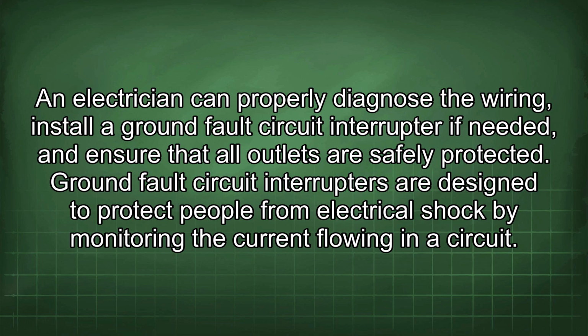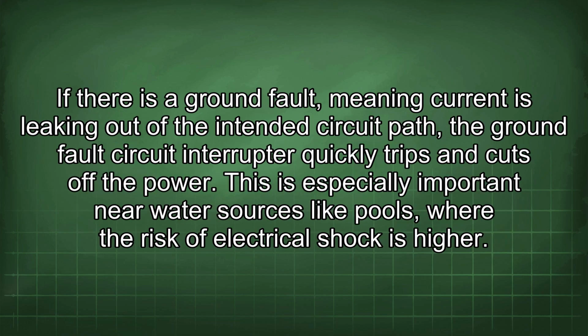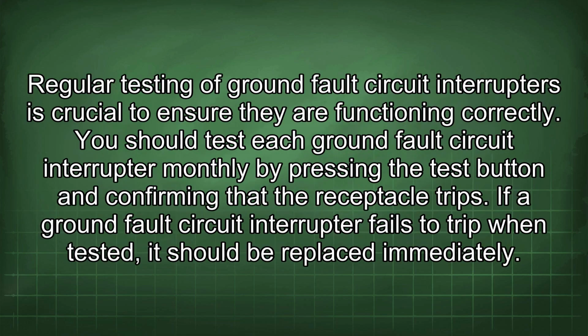Ground fault circuit interrupters are designed to protect people from electrical shock by monitoring the current flowing in a circuit. If there is a ground fault, meaning current is leaking out of the intended circuit path, the ground fault circuit interrupter quickly trips and cuts off the power. This is especially important near water sources like pools, where the risk of electrical shock is higher. Regular testing of ground fault circuit interrupters is crucial to ensure they are functioning correctly. You should test each ground fault circuit interrupter monthly by pressing the test button and confirming that the receptacle trips.